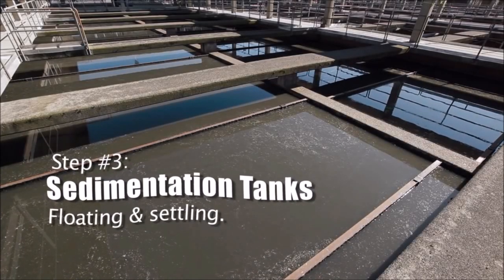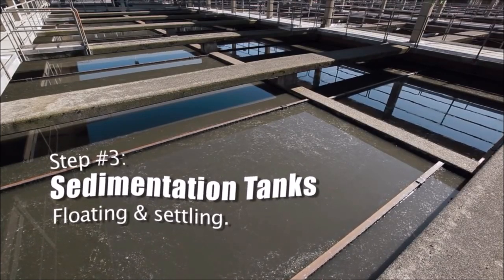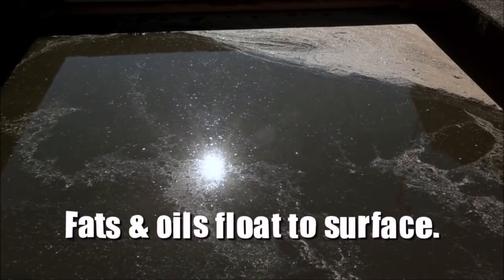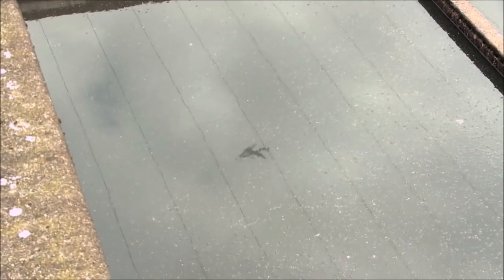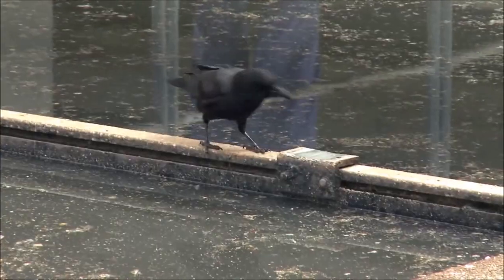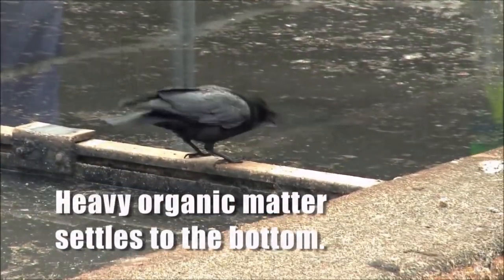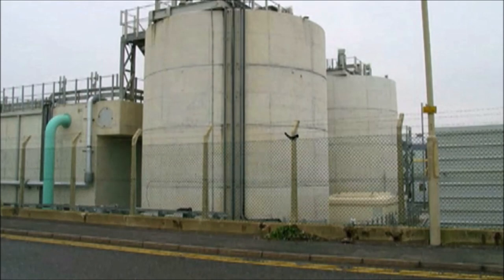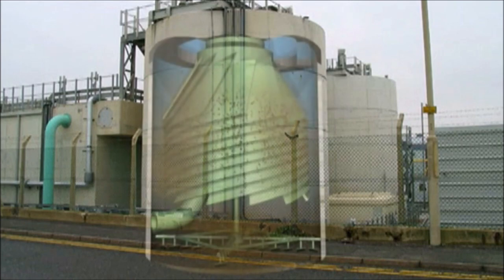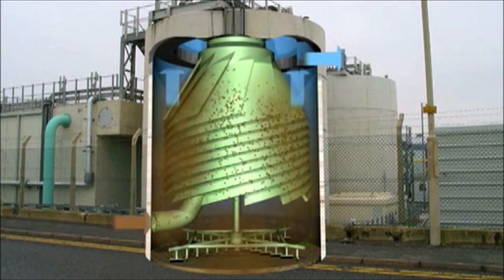As the water flows through this tank, it's moving very, very slowly. All the scum, fats, oils and greases are floating to the top of the surface. So we're going to collect all these fats at the front of this tank, and all the heavy organic matter is settling down. The primary settlement treatment process removes a large proportion of the solid waste. This spiral tank system is used where there is limited space. As the spiral rotates, the solid particles settle on a series of plastic plates and drop to the bottom of the tank as a sludge.